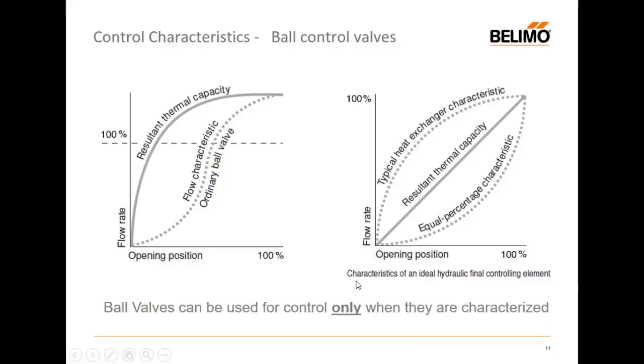But if I were able to characterize the control valve, if I'm able to limit the flow in the opening position here, slow it down and then graduate the flow so it rises on this axis, and my cooling coil, which is shaped like this, is the mirror opposite, then I will get equal percentage, because what I will get is a proportionality between the movement of the valve and the power from the coil, from the heat exchanger. We've called it a heat exchanger. It's actually a cooling coil, which is a type of heat exchanger. Could be a fan coil, might be an air handling unit.